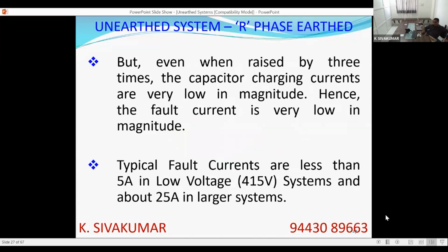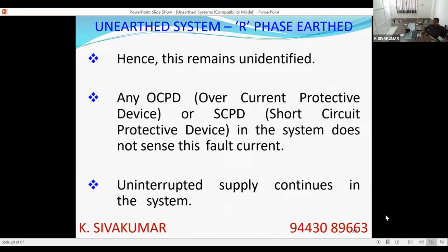So no overcurrent protective device, whether you provide an overcurrent relay or a short circuit relay, and these relays are set to 100% and more, will sense this 25 ampere or 5 ampere. The OCPD or SCPD in the system does not sense it. Since there is no fault detection and tripping, uninterrupted supply continues in the system.